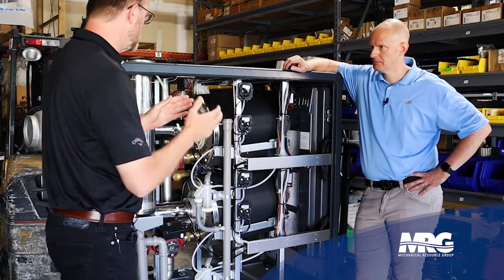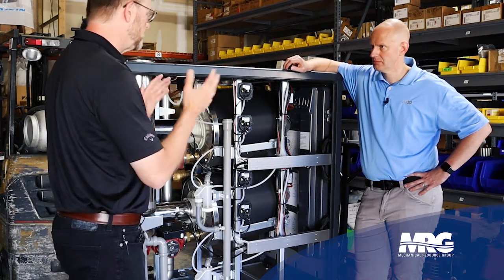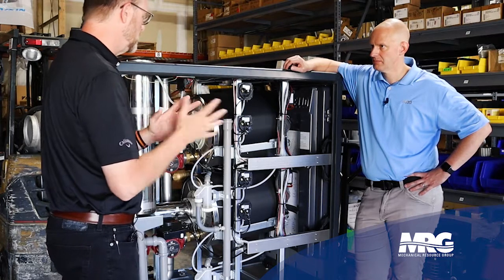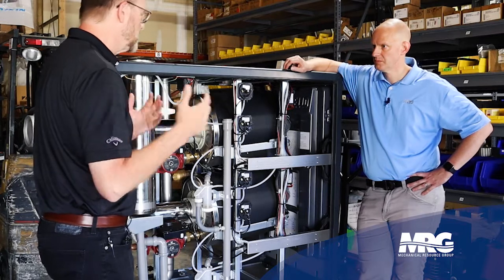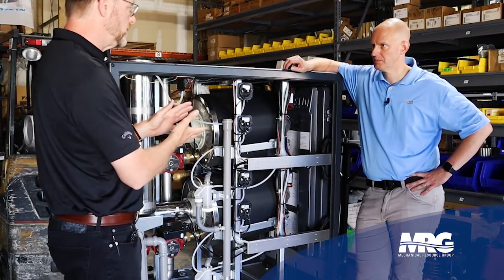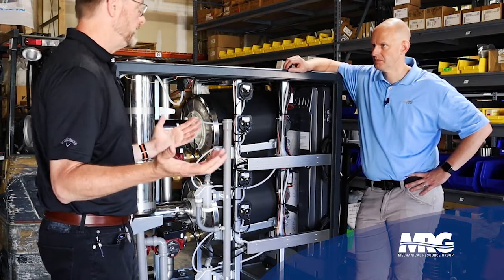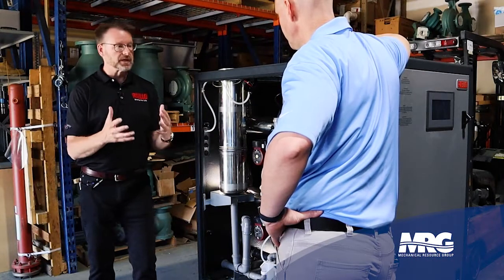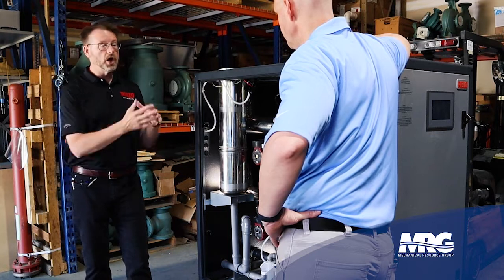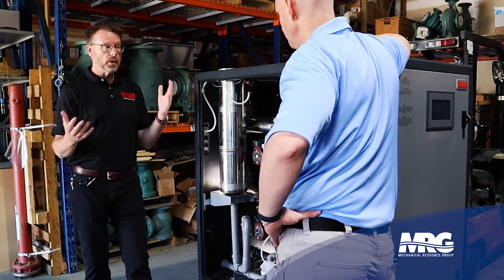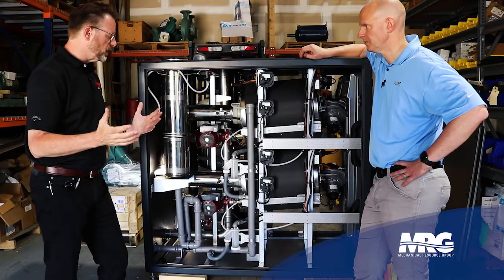We had a challenge with a flow switch where the flow switch wasn't indicating that flow was occurring. We also then, Tommy had been on a call where the circulator had failed. So it wasn't a bad switch, they actually had no flow. And we discussed the fact that that circulator was not readily available and he had to bring it in, and that all of the capacity was down while that circulator was failed.